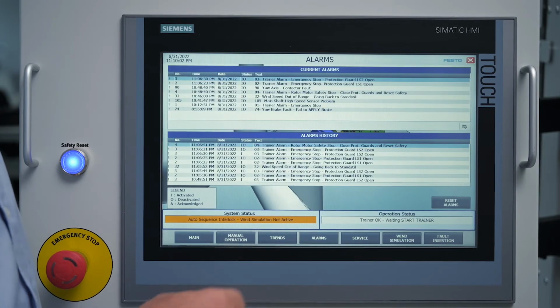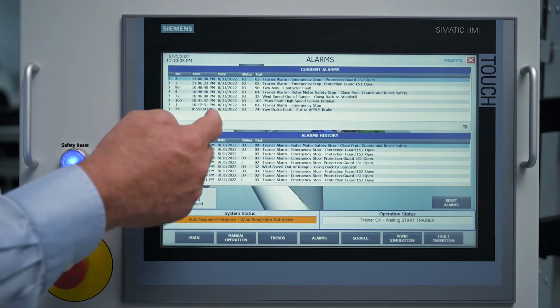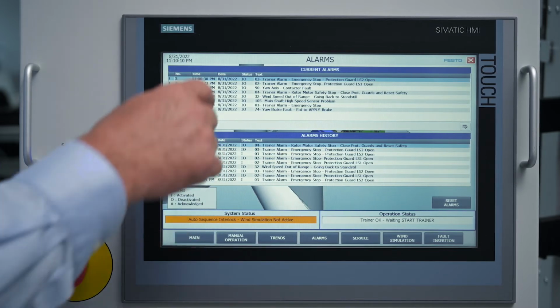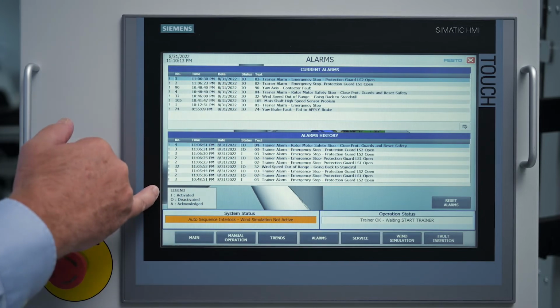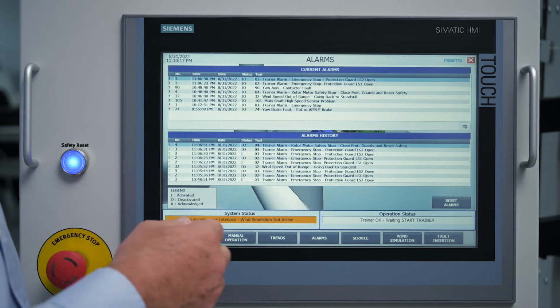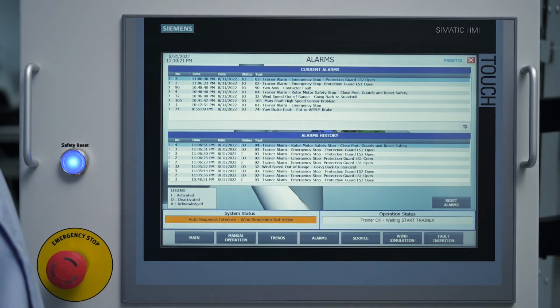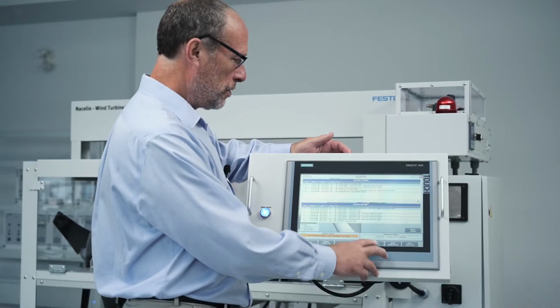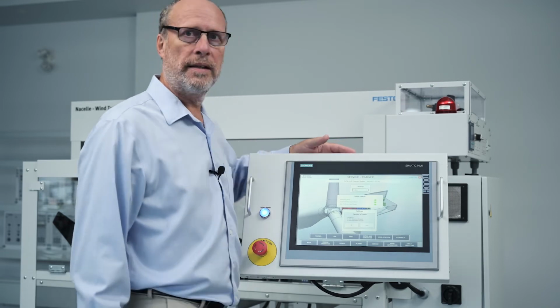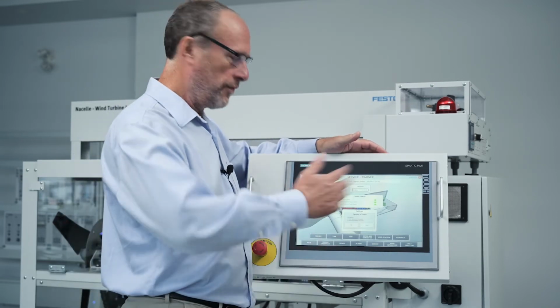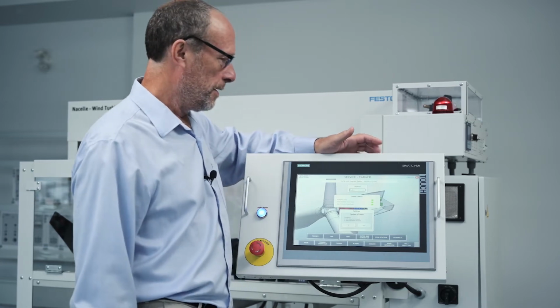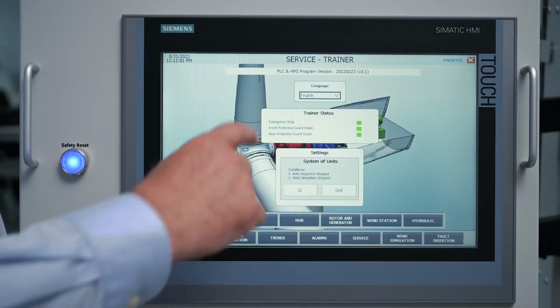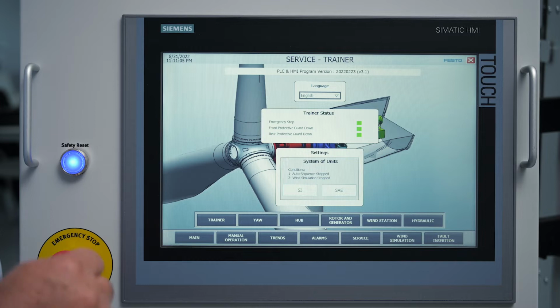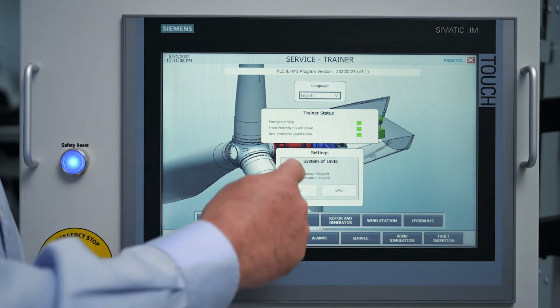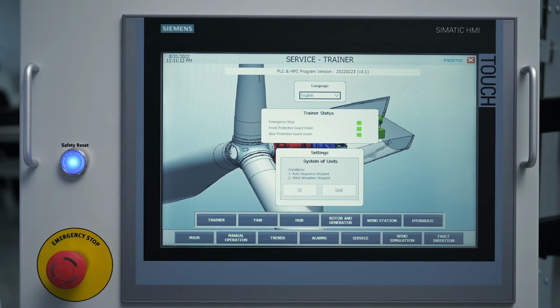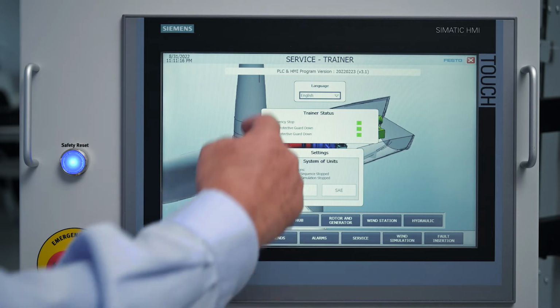After that, you have the alarm page. So here you have the history of the alarms on the machine. You have the current status of the alarm, which could be activated or acknowledged or any else. And then here you can reset if there is any active alarm. You have also here a service menu where you can set parameters. So the units, if you want the international system or the SAE. In this case, you can select language. Four languages are there already, but you can enter your own if needed. You have the choice of the units, metric or SAE, and you have the trainer status as well.